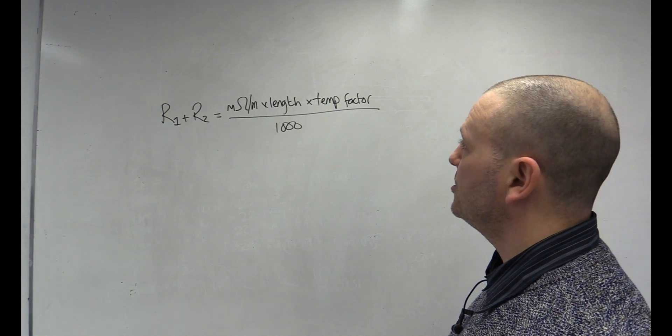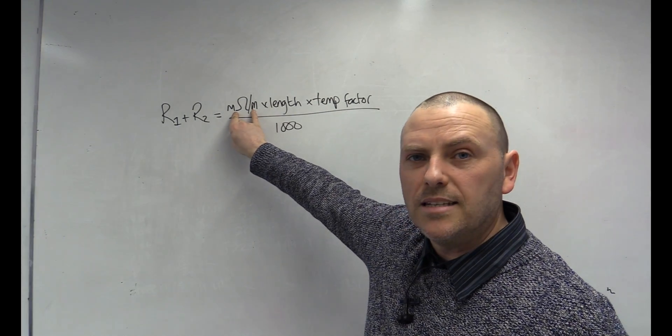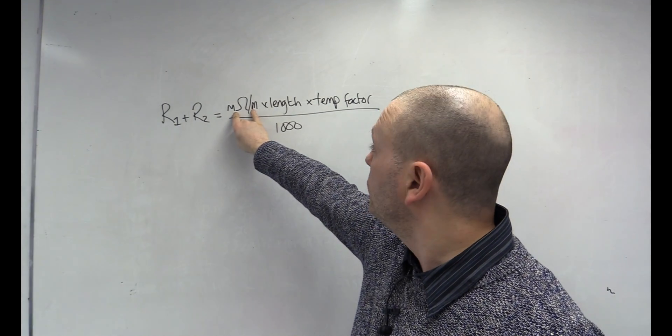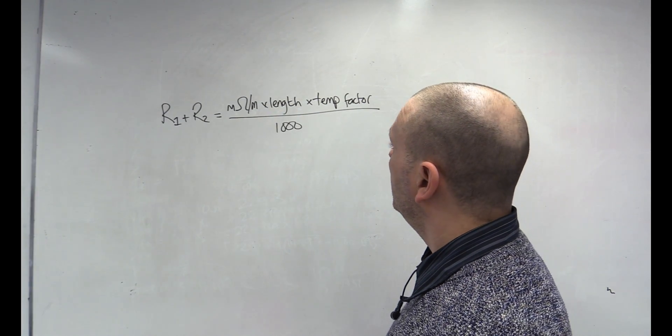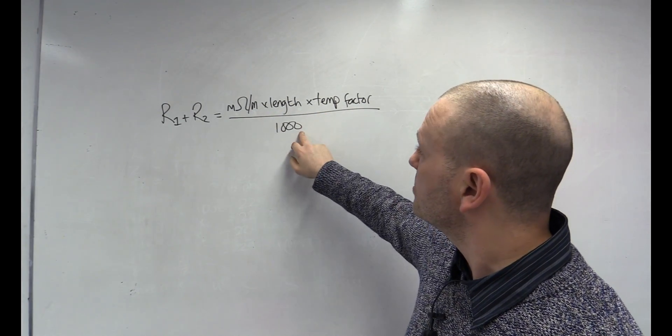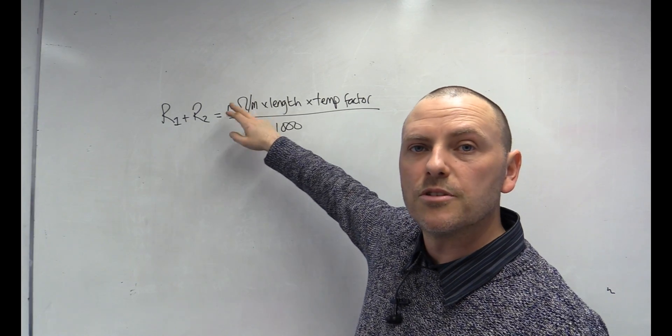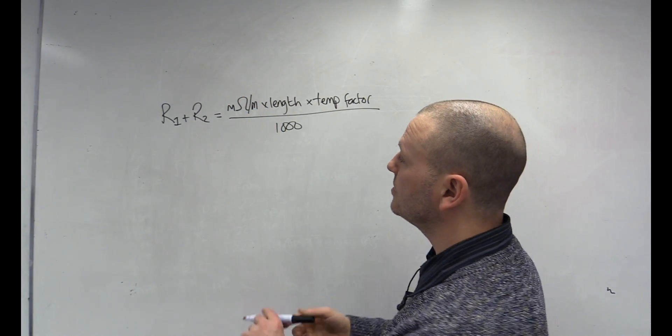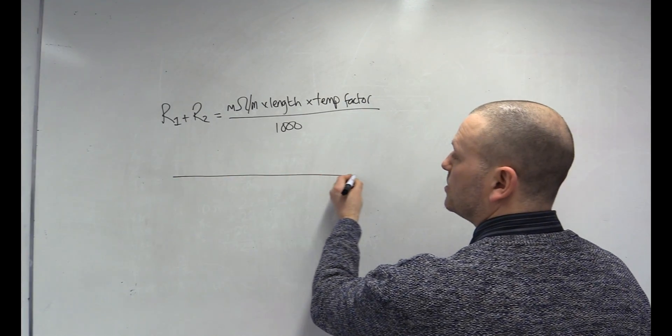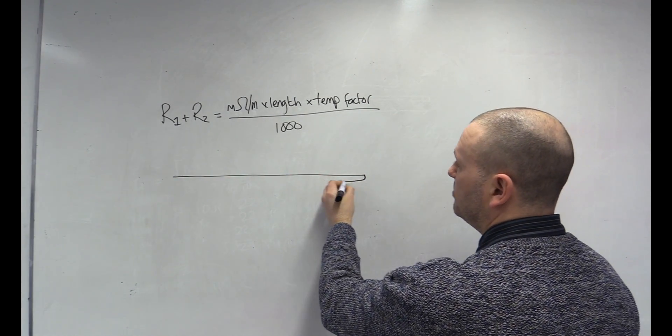And that goes here. Other than that, it's just a value per meter, which is given in table I1, times the length of our circuit, and we divide it by 1,000 here, to change it from milliohms to ohms. And that's going to give us the resistance of our live cable to our end of our circuit, and then back again.